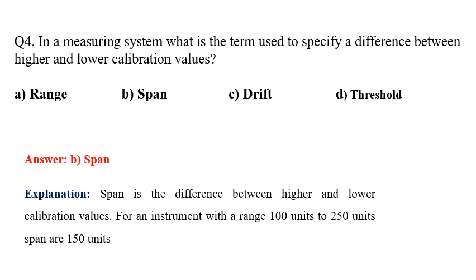For example, with a vernier caliper, the range may be 0 to 25 mm or 0 to 10 mm. Similarly for a screw gauge or micrometer, it is generally available in the range of 0 to 25 mm and 25 to 50 mm. Here 0 to 25 mm is the range, and the difference, 25 mm minus 0, is the span. So span is the difference between the higher and lower calibration value, while range is defined from a minimum to a maximum value.